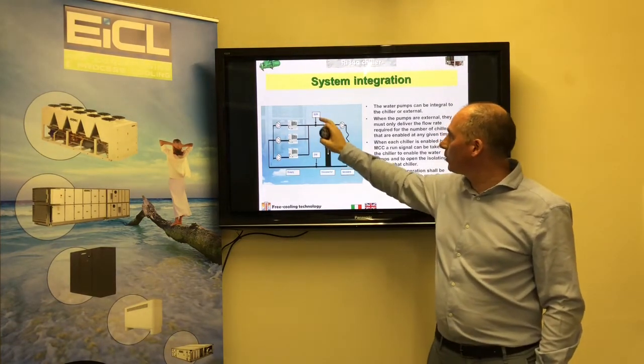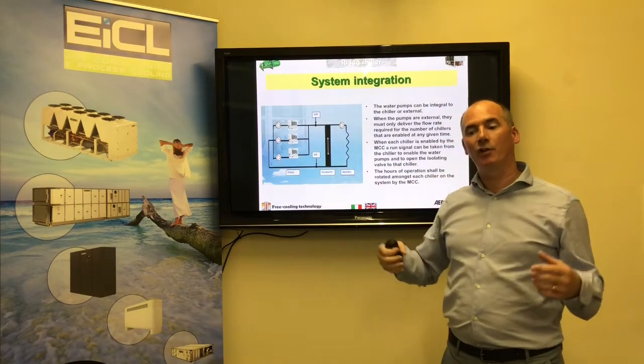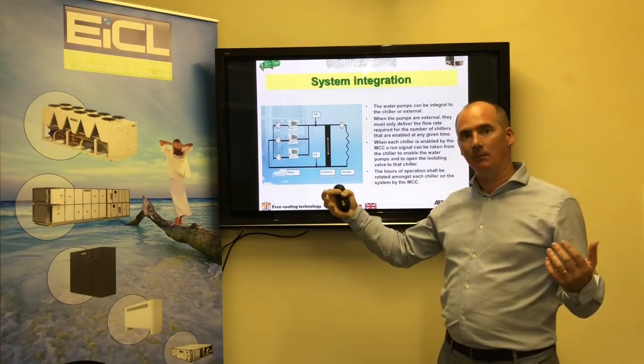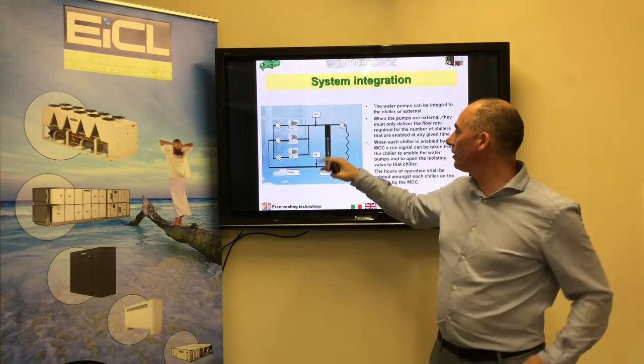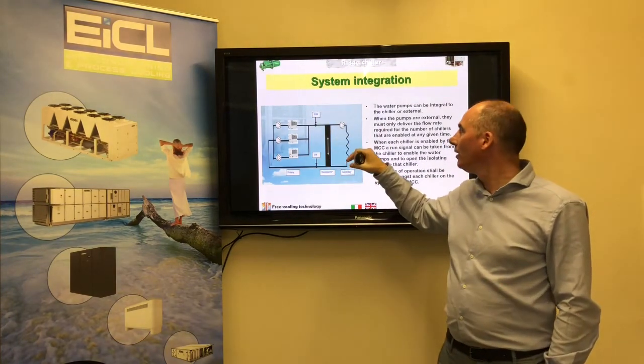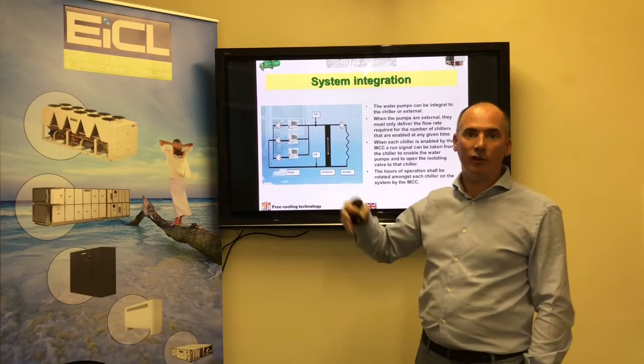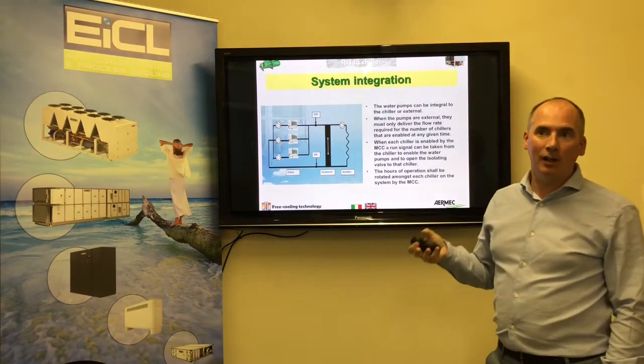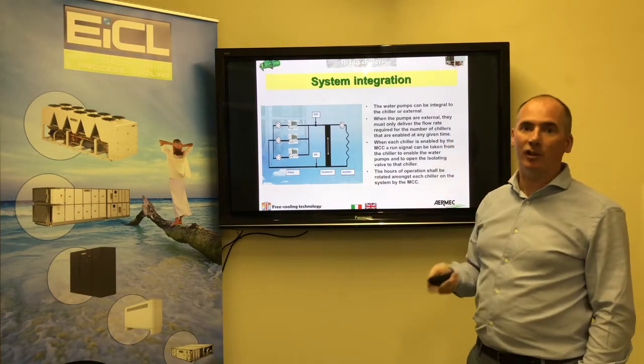You need to locate a temperature probe on the common inlet, common outlet, because you're now analysing the system load. And obviously as the return temperature increases, you have a higher delta T, the MultiChiller controller realises the load is increasing and interprets the load, and consequently enables the chillers as required.